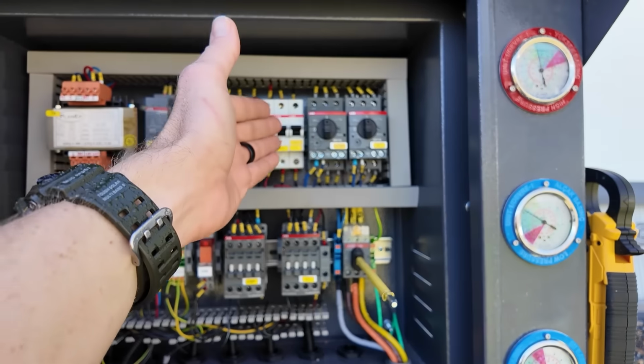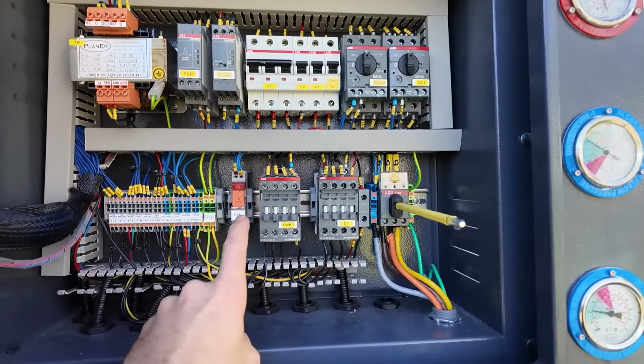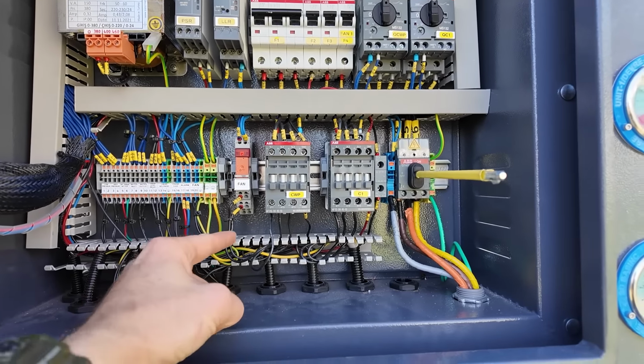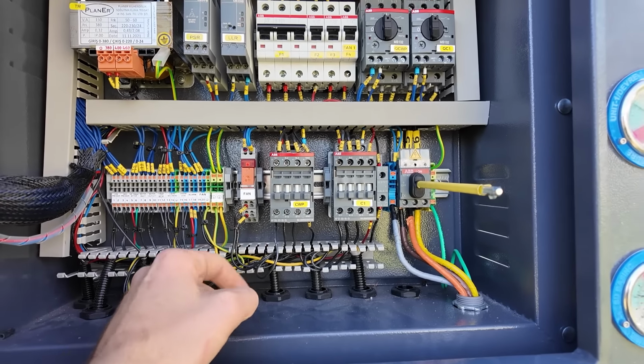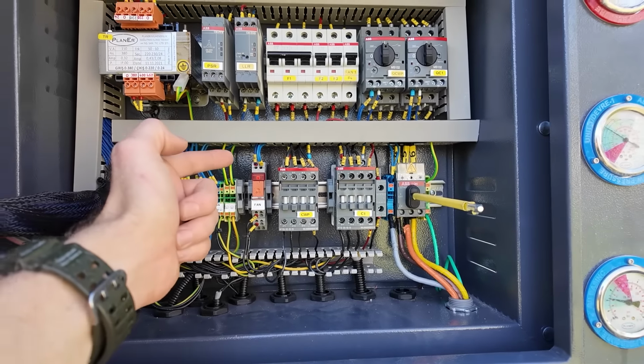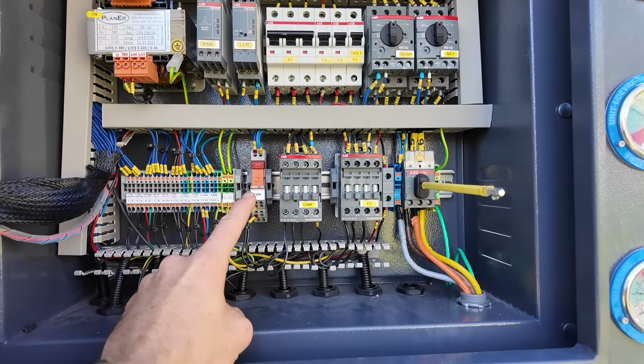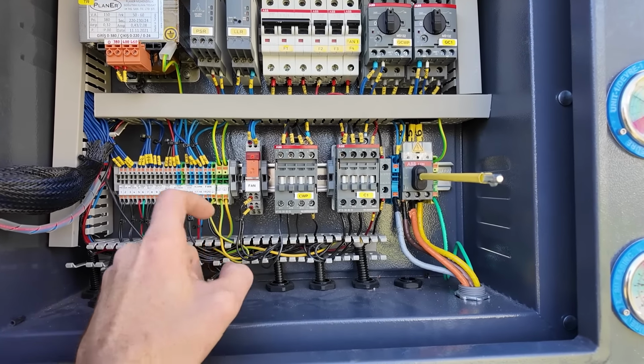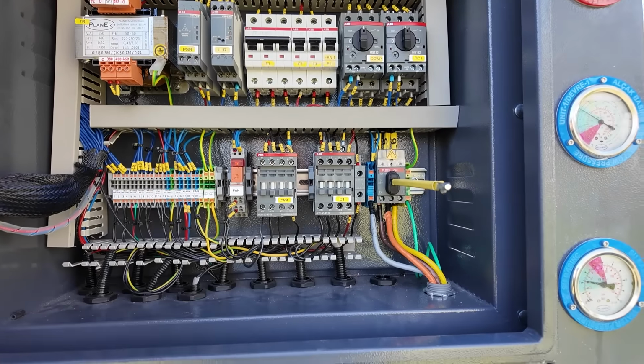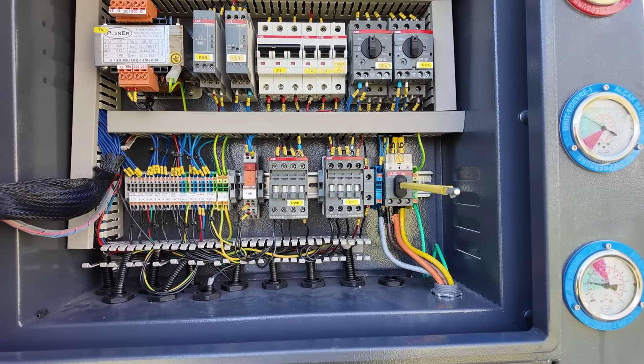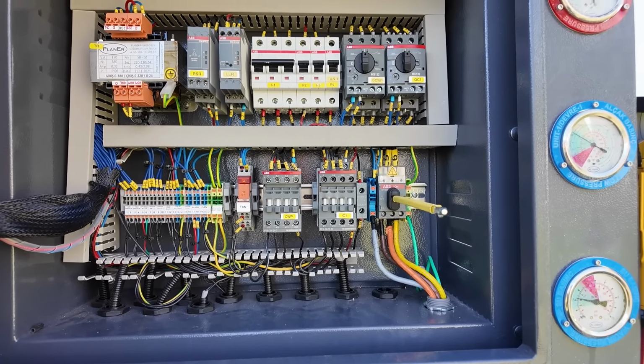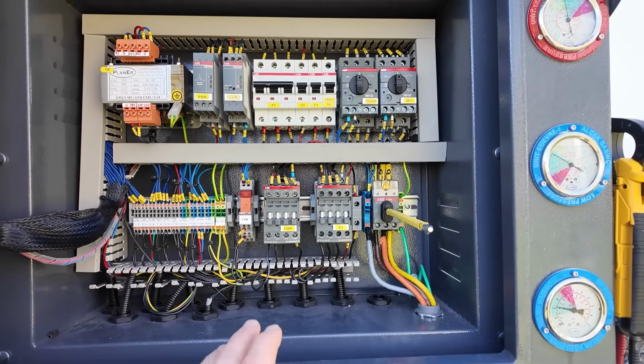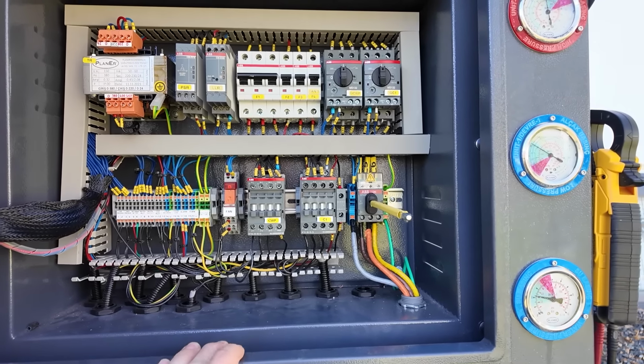So what I've done is I've cycled the power on the breaker, ensure that it was good. Then I found down here on this ice cube relay that I had power coming in on the bottom, but not the top. Now, when this relay gets energized with 50 volts on the top, it's supposed to close this ice cube relay and complete the connection for the fan outside. Now, this isn't a variable speed fan in regards to modulating the signal from a control board, from what I can tell, but there is something within this system that tells it, hey, run the fan.